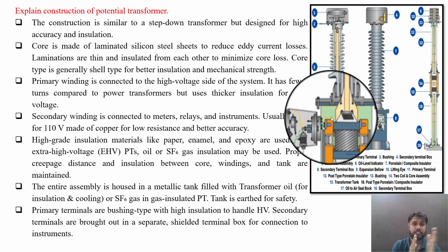High grade insulation materials like paper, enamel and epoxy are used. For extra high voltage PTs, oil or SF6 gas insulation may be used. Proper creepage distance and insulation between the core, windings and tanks are maintained.